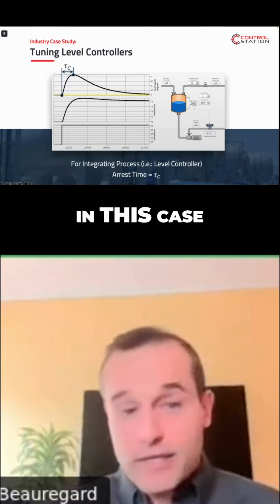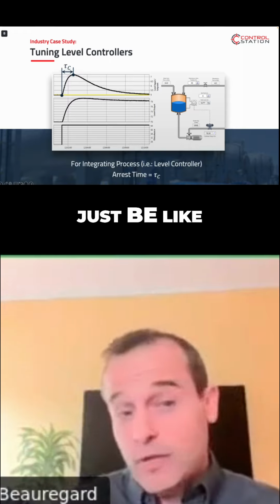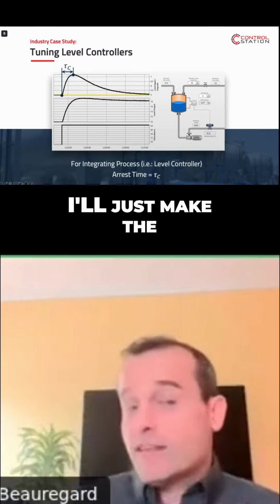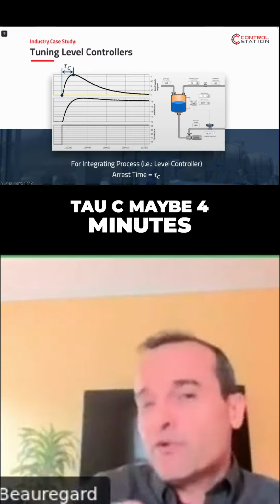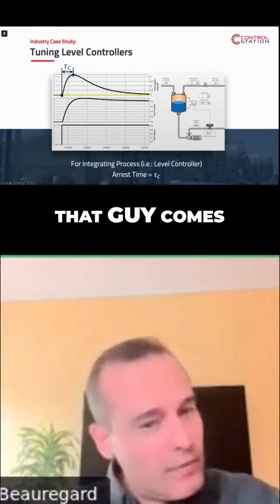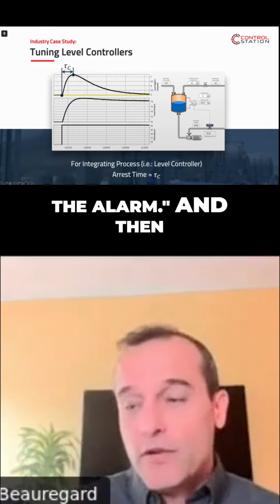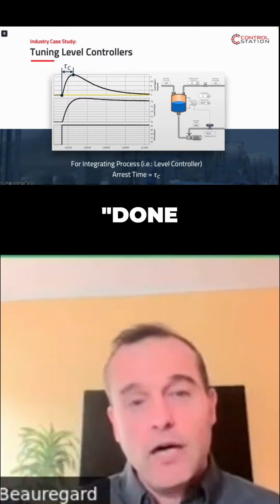Okay, so in this case, that's perfect, because you can just say, well, okay, 5 minutes, I'll just make the tau C maybe 4 minutes, 4.5 minutes, right? Just to make sure that that guy comes around before we trip the alarm, and then you can just say, done, on to the next one.